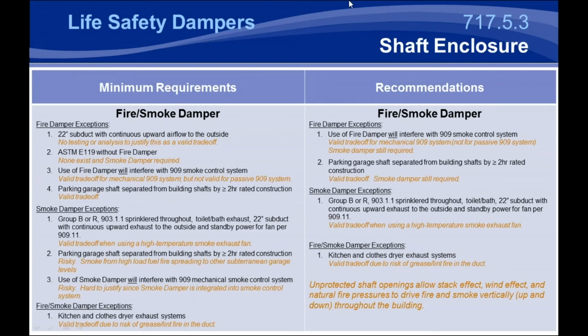The next most critical type of assembly that we'll talk about are shaft enclosures. And basically, shafts are the way to move air up and down a building across multiple stories. Because of that, there is a very high risk for smoke transfer throughout the building if shafts are not protected with any type of smoke control or fire smoke control. In order to fully operate a building, basically to keep the occupants safe in these emergencies and reduce the loss of life, the minimum requirement is going to be a fire smoke damper. So you need fire and smoke protection.